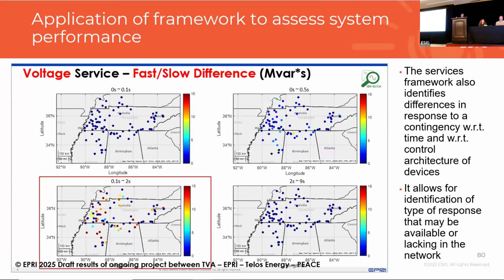Right after an event, between 0 and 0.1 seconds, there's very little difference between a fast or slow parameterization. Some difference starts cropping up around the 0.5 second region, but most of the difference in response pops up between 0.1 seconds and 2 seconds. So a system operator can take from this that the interconnection or performance requirements they've set might give the most benefit only in that 0.1 to 2 second window after an event, and if that's a cause of concern, they can use this framework to further refine their interconnection requirements.